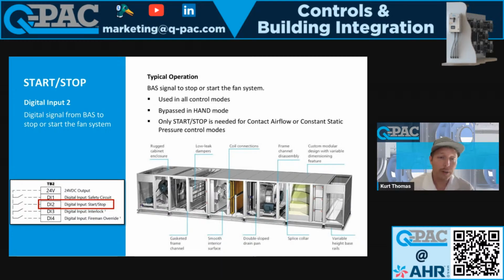So again, if you want to bypass this and put a jumper in, you can. And then whenever you don't want the fans to run, your BAS can just send a 0-volt signal. But it is pretty common for start, stop, and a 0 to 10-volt signal to be used. And it's pretty basic. But hand mode does bypass it. So if you're in hand mode, then it's not going to look for that start signal from your BAS. So hand mode, like I said, bypasses everything and bypasses our internal PLC. We don't want any errors with our PLC or anything to stop you from actually operating these fans.